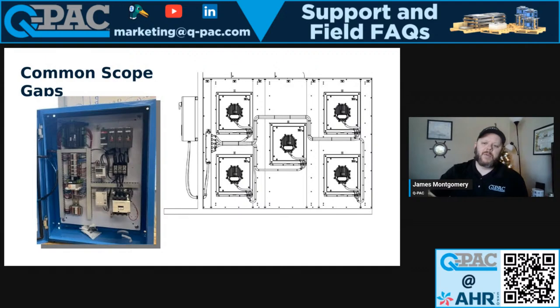But the scope gap is, we're used to our electrical trades running high voltage. They will push conduit, it'll be properly bonded, they'll bend it all nice and it'll look great, and they'll run it from the source to the control panel, from the control panel to the quick connect box, and then they leave the job. Well, controls or low voltage has to be run. And I don't mean controls coming from the BAS, I mean low voltage wires between the control panel and the quick connect. So I'm going to beat on my desk and say, this is a big deal. Check your scopes. If you're a mechanical contractor or if you're reviewing the submittals, you need to double check and make sure that somebody remembers that.